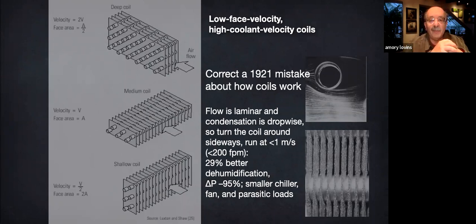So if you take the usual deep, dense cooling coil at the upper left and turn it around sideways to make a shallow, sparse coil at the lower left, and then you blow the air through it slowly, less than a meter per second, less than 200 feet per minute. That's a quarter of the normal face velocity. Then you preserve those precious droplets and their extra surface area. And that increases dehumidification 29% per unit of sensible cooling. It cuts the airside pressure drop that the fan power has to fight by 95%, a factor 20, and it shrinks the evaporator load on the chiller, and it shrinks the entire cooling system. I understand Carrier Corporation has long had such coils in the lab with production intent, and I'm eager to see them in the market. Of course, if you used radiant cooling, you wouldn't need the coils or the fans.